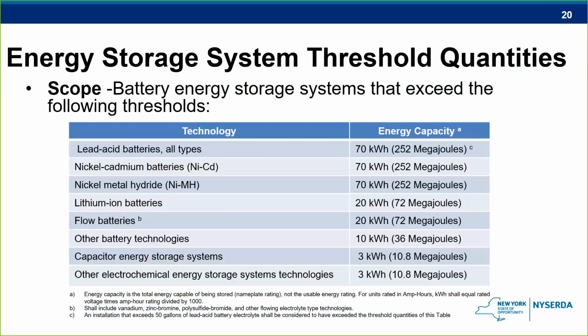All right, so most of what we'll be talking about today are the code requirements for systems that are not subject to the residential codes and that exceed the capacities outlined in the new fire code as shown on this slide. These will encompass the majority of commercial and utility-sized installations, and most of the upcoming slides are going to be pointing out code requirements for these. We'll take a few minutes right before, about an hour in, to go through a little bit of the residential requirements as well, but for the most part, we're focusing on these larger systems subject to the fire code.